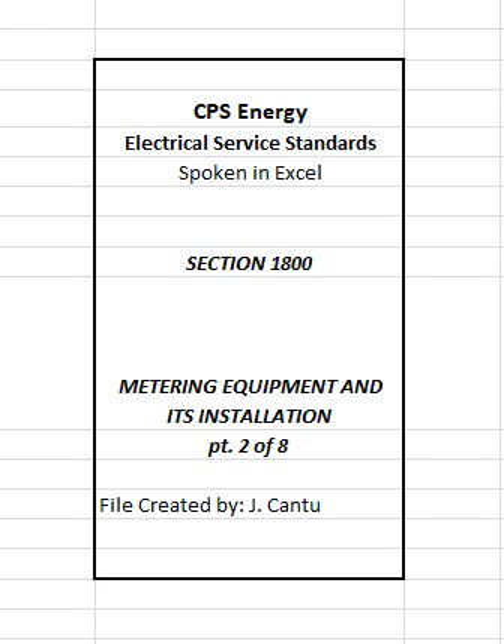C. Standard instrument transformer enclosures. CPS Energy furnishes the following standard weatherproof instrument transformer enclosures for installation by the customer. CPS Energy will work with electrical contractor on installation of instrument transformers so as to facilitate the installation of service conductors and eliminate unnecessary splices within enclosure, refer to Table 1801 and Figure 1811. 1. Code 10, 26 inches H x 30 inches W x 9 inches D, for 2 to 250 kcm/phase or equivalent kcm in fewer conductors.